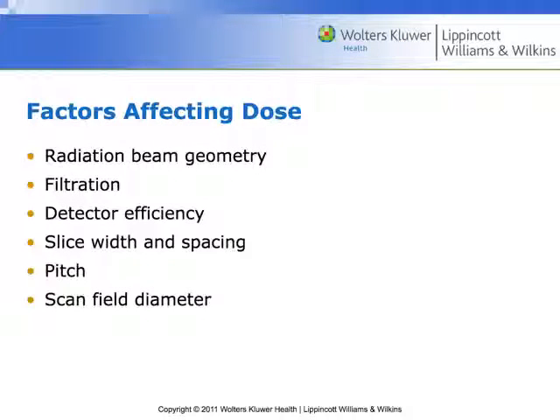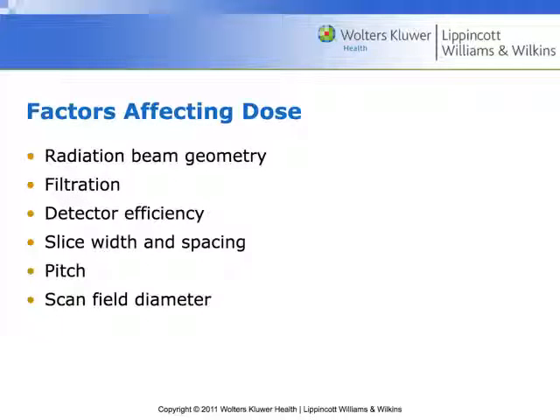Here are the factors that affect patient dose — some we have control over, some are determined by the protocol. Radiation beam geometry: specifically whether the rotation arc of the CT scan is 180 degrees, 360 degrees, or if there's an over-scan like with a fourth-generation scanner at 400 degrees — that additional arc causes additional dose. Filtration: CT uses a great deal of filtration, so the beam is significantly harder than conventional radiography, which does affect dose — and that's a good thing.